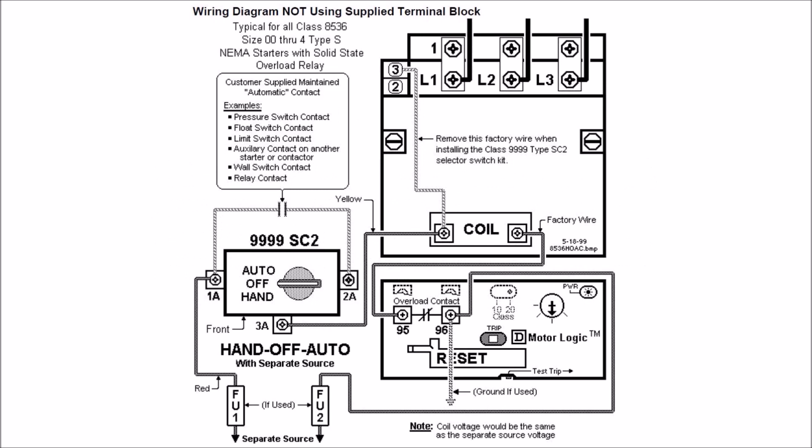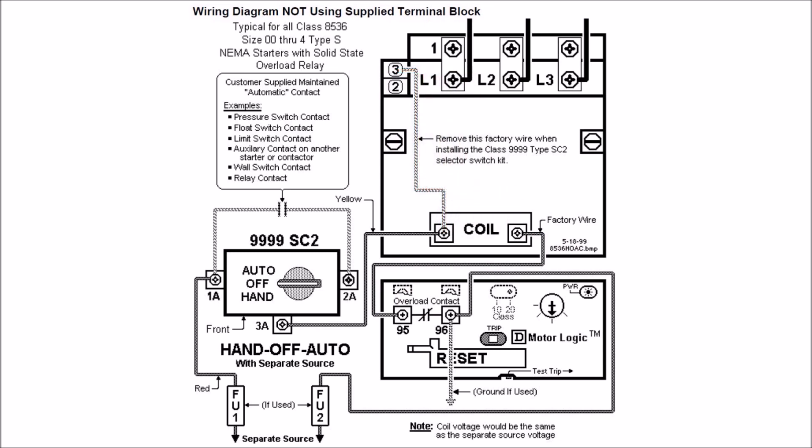For wiring for the 9999 SC2 handoff auto selector switch, it's standard two-wire control. When you get the starter itself for the Type S under separate control, you'll have just a wire from 95 on your overload relay to the left-hand side of your coil. No other wires will be installed except this jumper terminal from three in your holding circuit contact to your coil, which you won't use here.